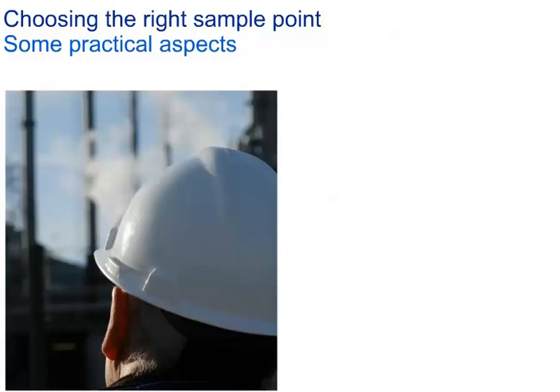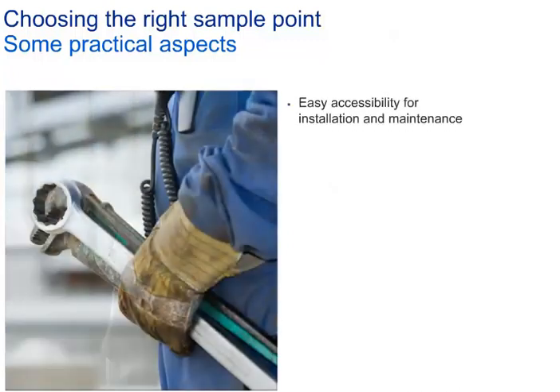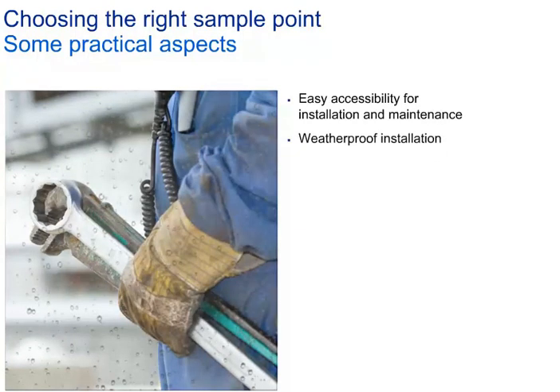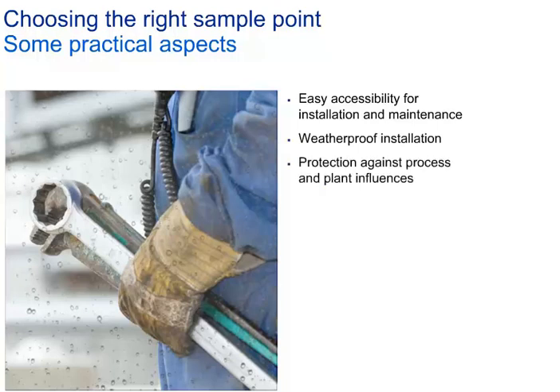At the very beginning of the measurement, the customer has to choose the right sampling point in a process. Here are some practical aspects: if possible, select a point with easy accessibility for installation and maintenance; weatherproof installation should be preferred with protection against direct sun and rain; and the sample point should be protected against process and plant influences like pressure changes, heat, or dirt.